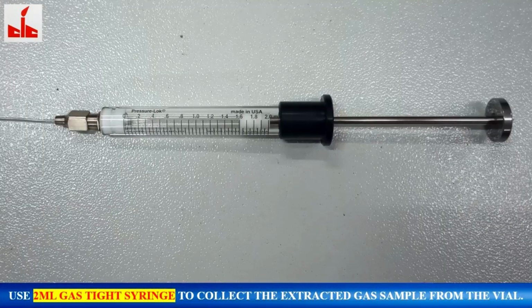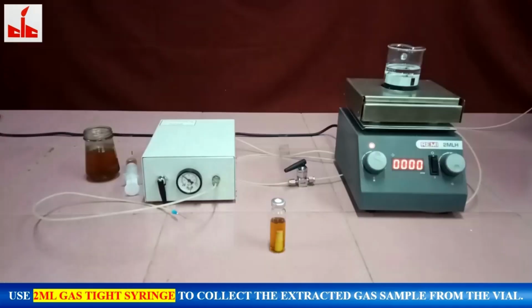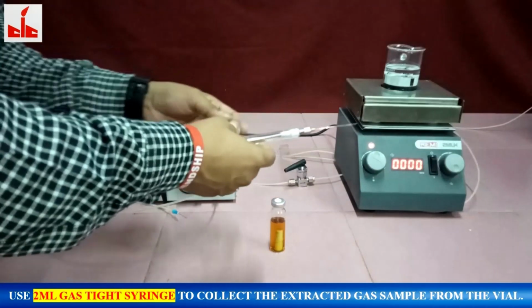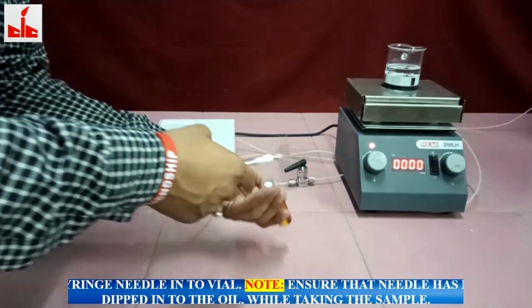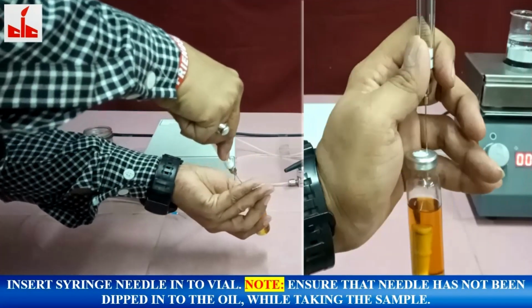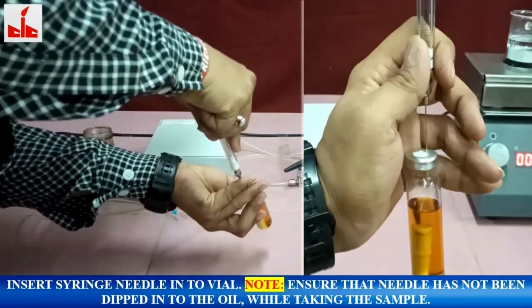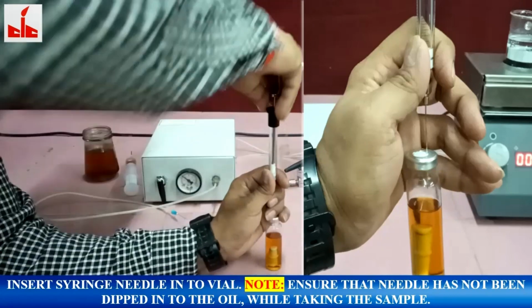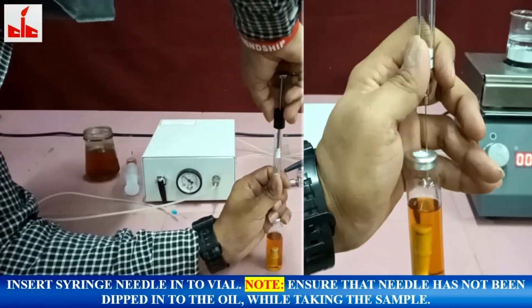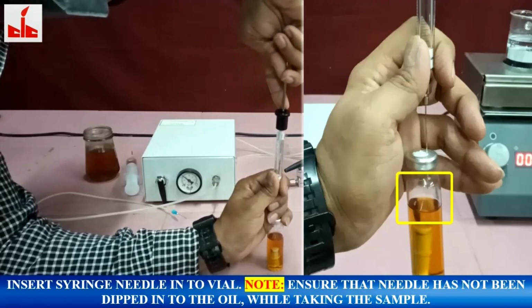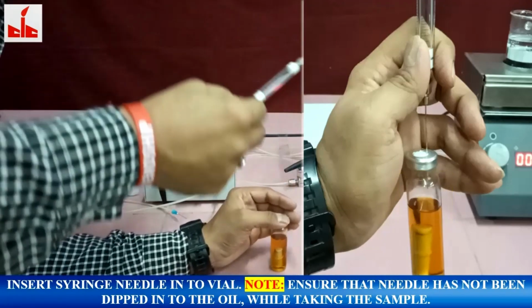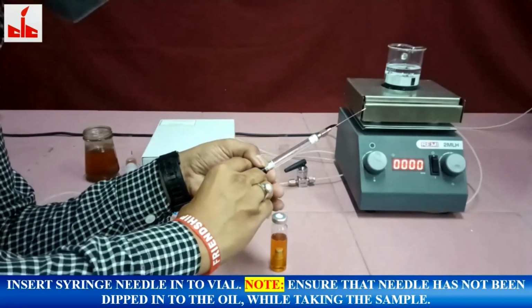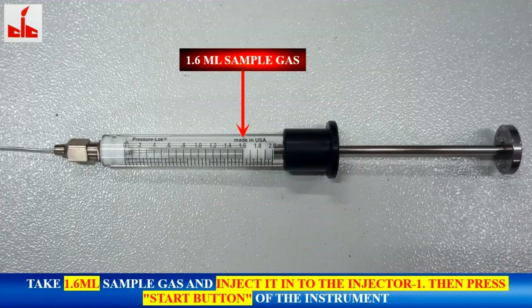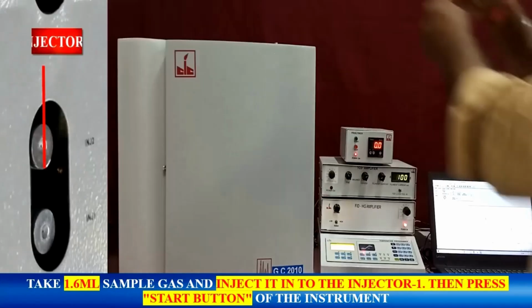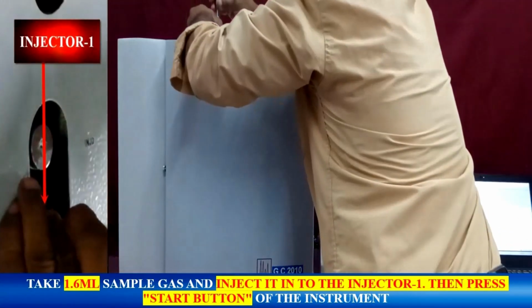Use a 2 ml gas tight syringe to collect the extracted gas sample from the vial. Insert the syringe needle into the vial. Ensure that the needle has not been dipped into the oil while taking the sample. Take 1.6 ml sample gas and inject it into injector number 1, then press the start button of the instrument.